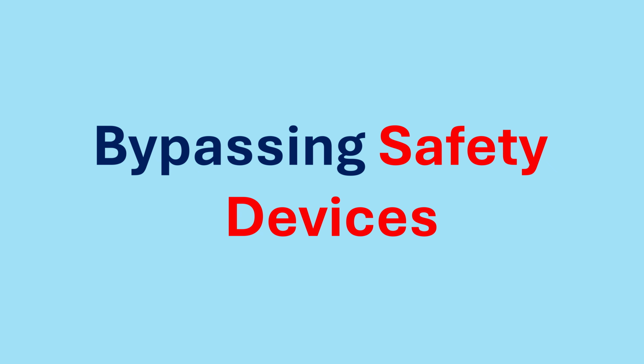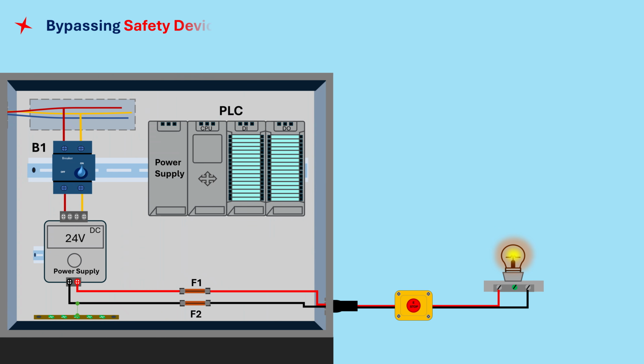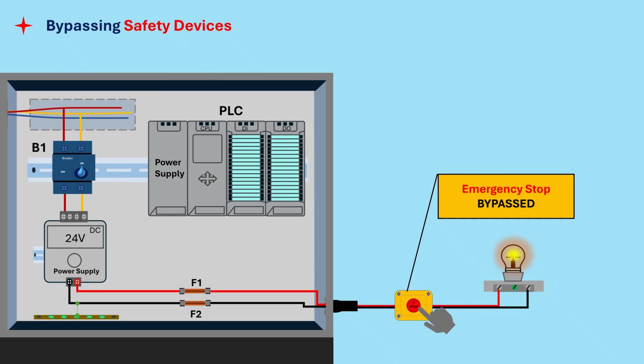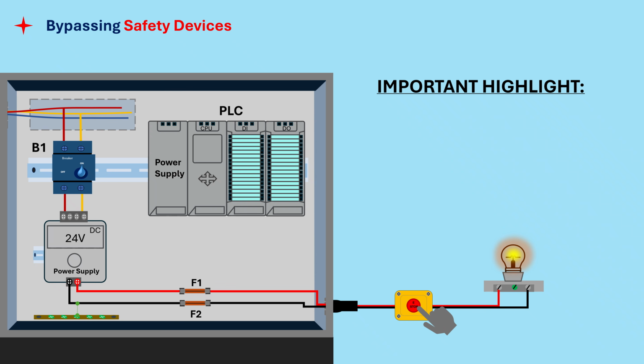Mistake number 8. Bypassing safety devices without documentation. There are times when a safety device must be bypassed for testing, but failing to record it or put it back the way it was is both unsafe and unprofessional. It endangers anyone working on the equipment and leaves you personally exposed if something goes wrong. Important highlight from mistake number 8. If you bypass it, restore it, and document it.